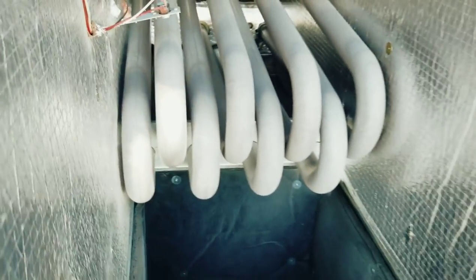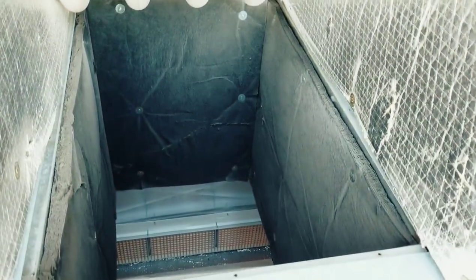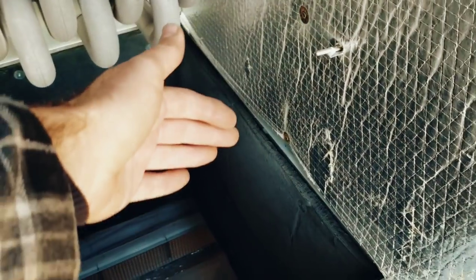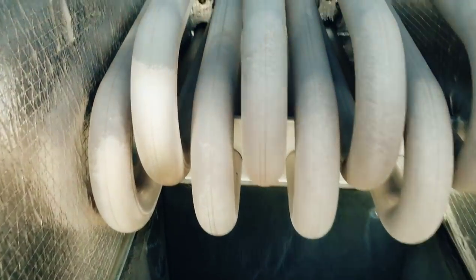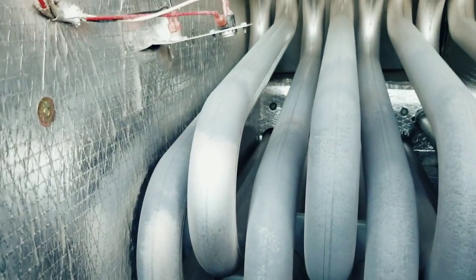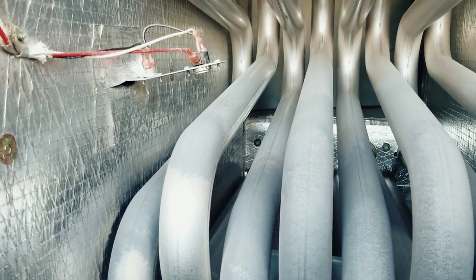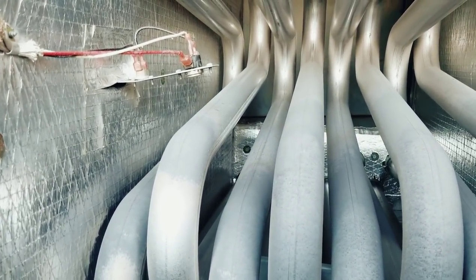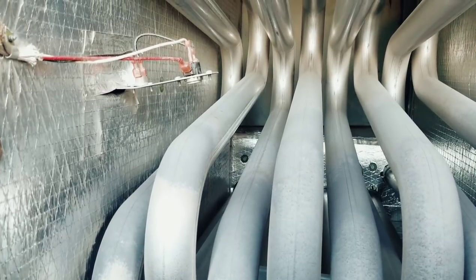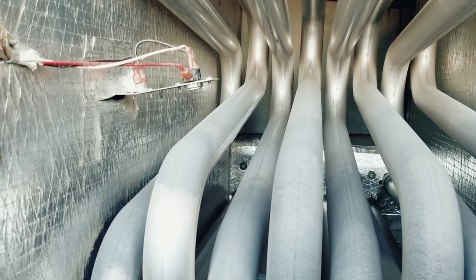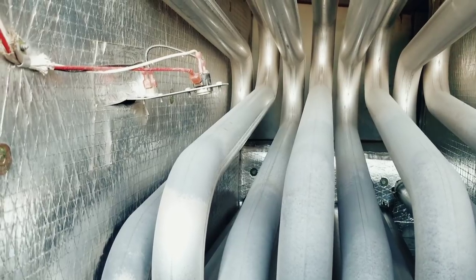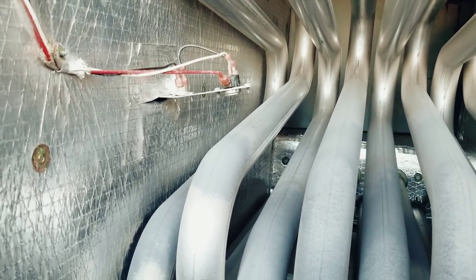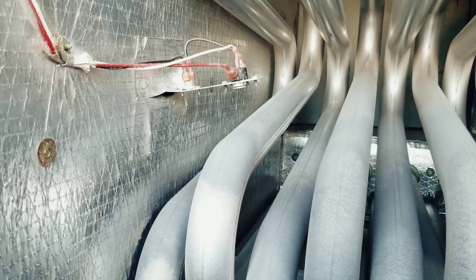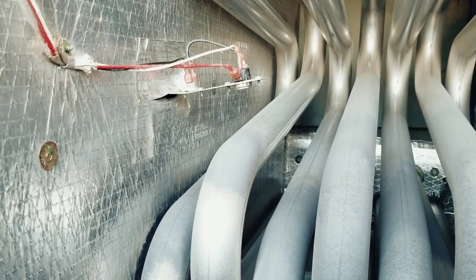All right. My type K thermocouple was just sitting inside the panel, probably somewhere around here. And we read about 160, 165 there. That limit assembly is right above the heat exchanger, so it would have been a lot hotter over there. Who knows how hot it got, but it got hot enough to trip that limit. And I believe that limit is set at 190 degrees Fahrenheit, the manual reset.